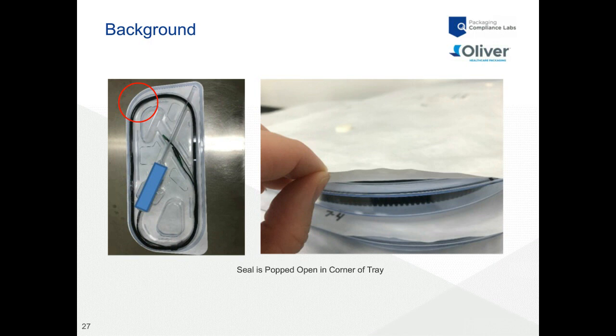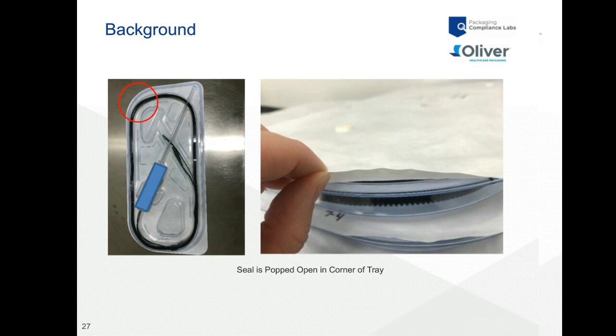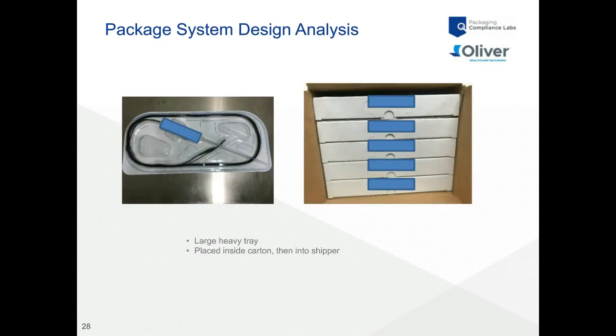The fourth example will be a little bit different. This is a semi-rigid thermoform tray with a Tyvek lid. In this case, we had a large, heavy, clunky device that went inside of a thermoform tray. We observed around 60 or 70% rate of failure, and that failure, shown in the image on the right, is a premature opening of the seal in that corner. So we need to ask ourselves, what could occur during transit testing that would lead to seals popping open like that?